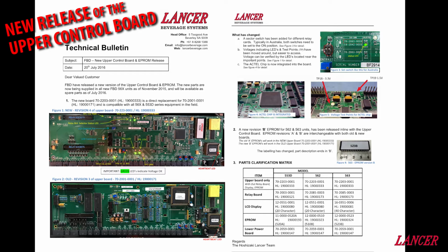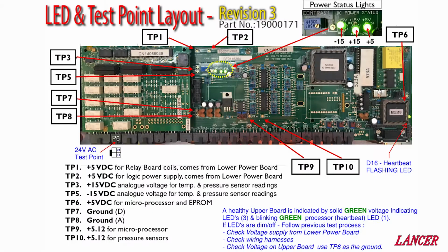Due to the release of the new upper control board in November 2015, we'll need to review 2 different versions of the upper control board. They are functionally the same, but have key differences that can cause some confusion, particularly with the position of the test points and LEDs and the relay board selector switch. This layout of the upper control board has been around since the beginning. It is identifiable by 3 LEDs that indicate the voltage status next to the blue contrast pot.